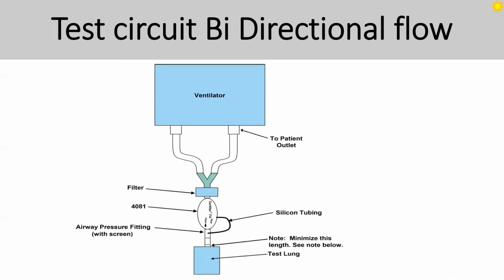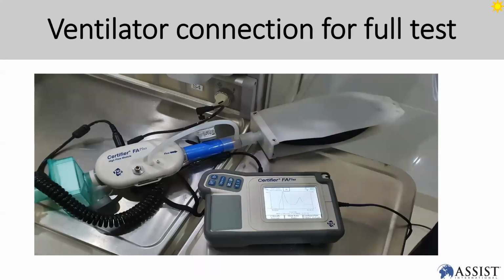So this is a bi-directional connection, a sample of the connection that you are going to do during your ventilator test. When doing a full ventilator test, this is how the connection looks. Remember, the HEPA filter should be on the end of the Y connector. You don't want any cross infection to your test tube. And you've got the test lung and your monitoring module.